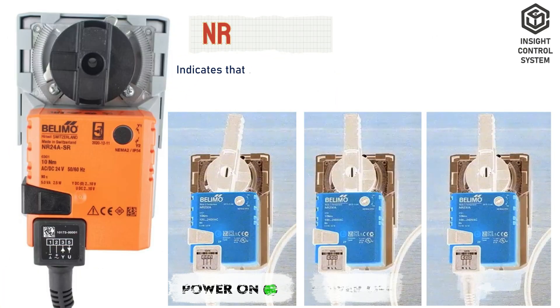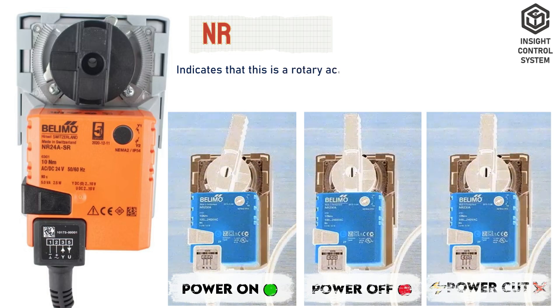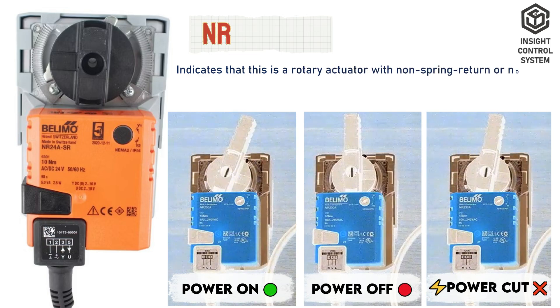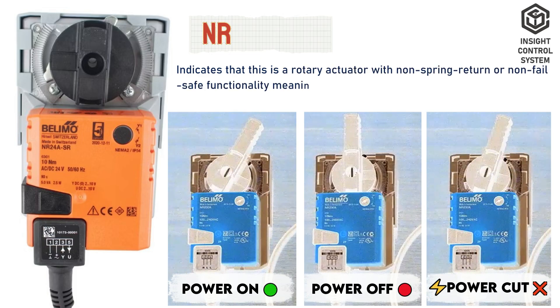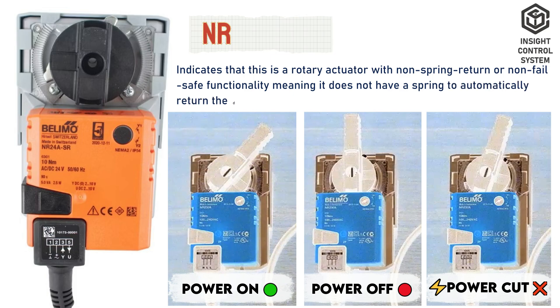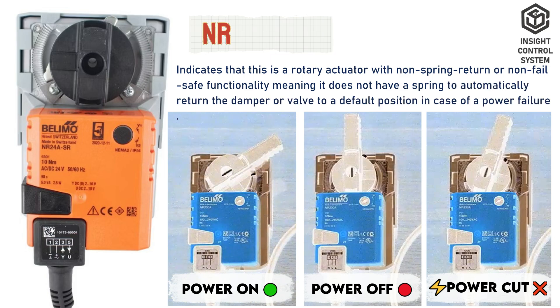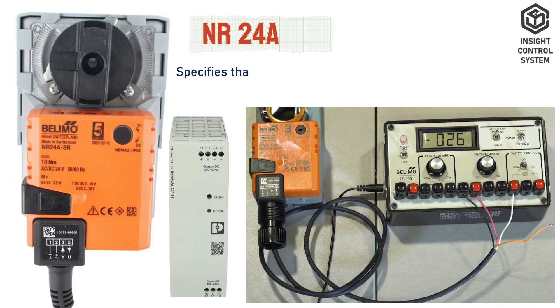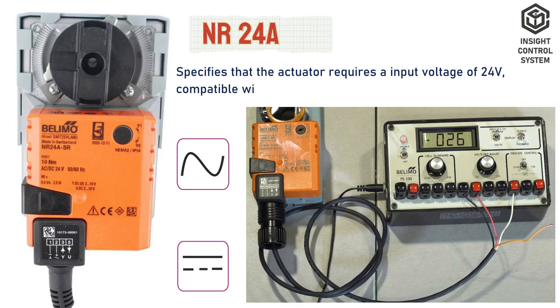NR indicates that this is a rotary actuator with non-spring return, or non-failsafe functionality, meaning it does not have a spring to automatically return the damper or valve to a default position in case of a power failure. 24A specifies that the actuator requires an input voltage of 24V, compatible with both AC and DC power sources.